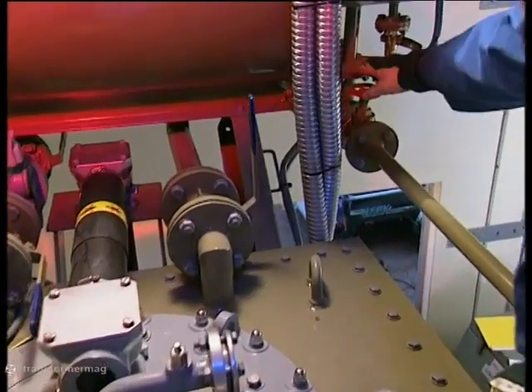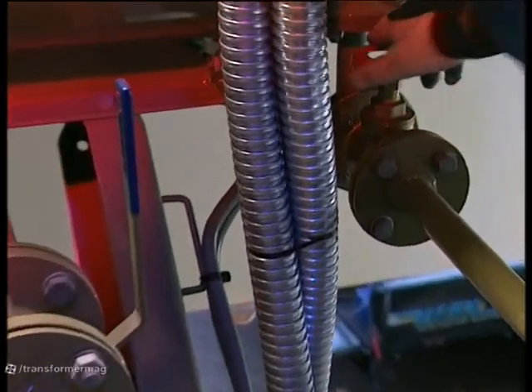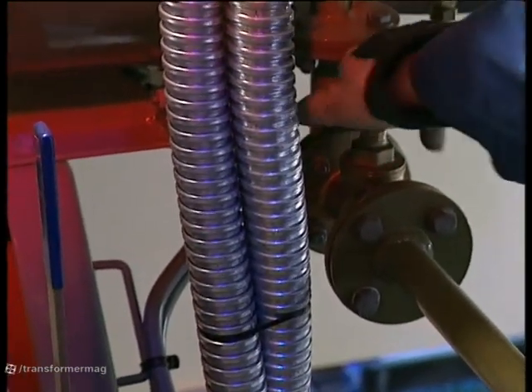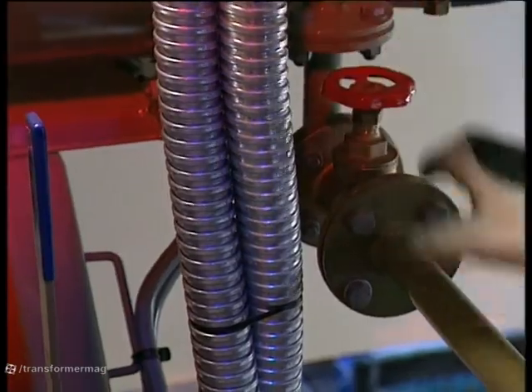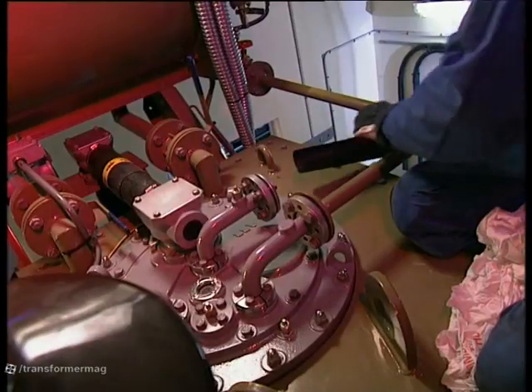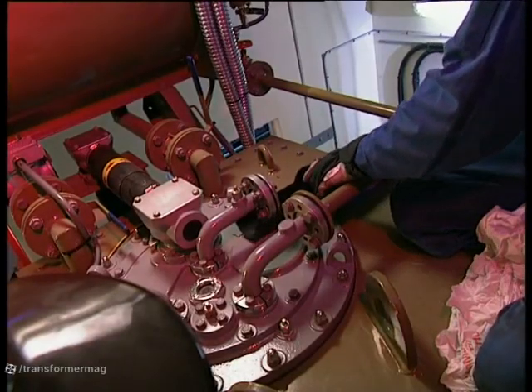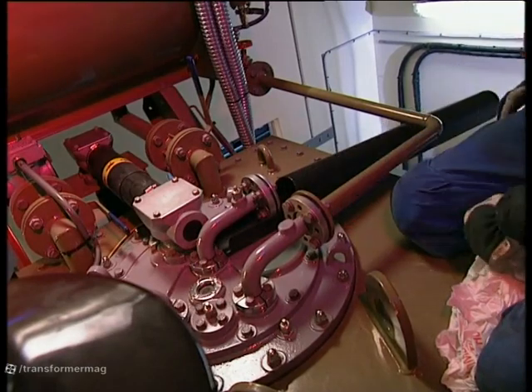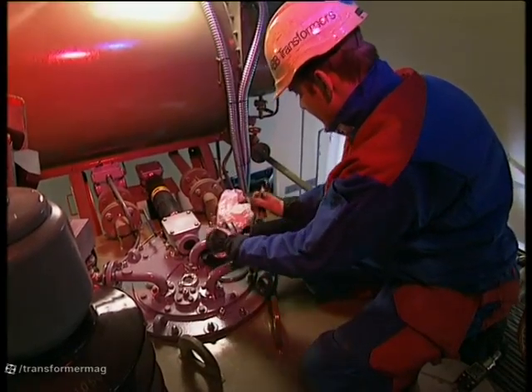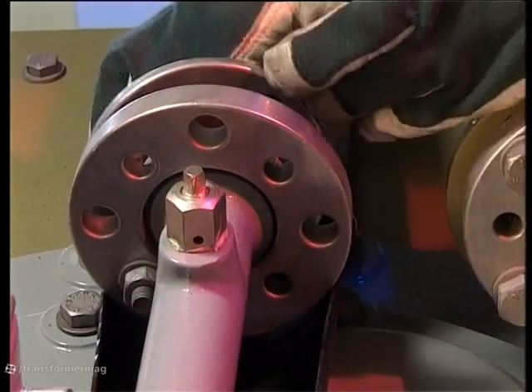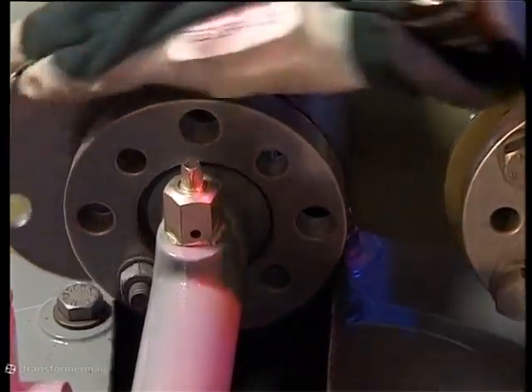The first step is to drain the oil. First, close the valve in the pipe to the conservator, expansion vessel. Make sure you're prepared to collect oil spilt as you work. Open a suitable pipe to drain the oil. Later models have a drain valve in the middle of the cover.